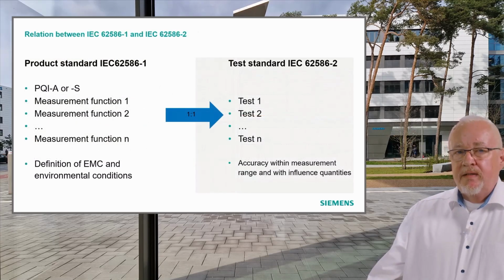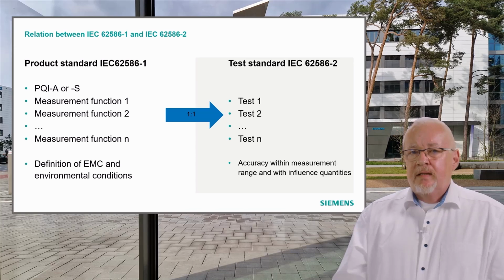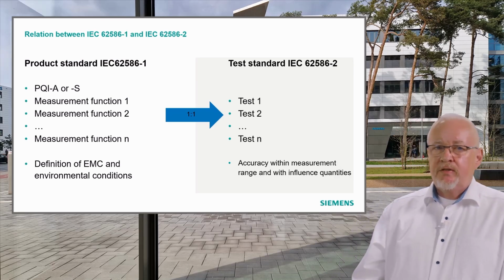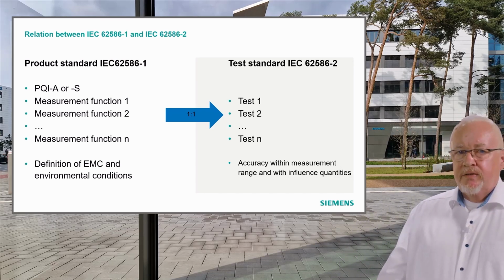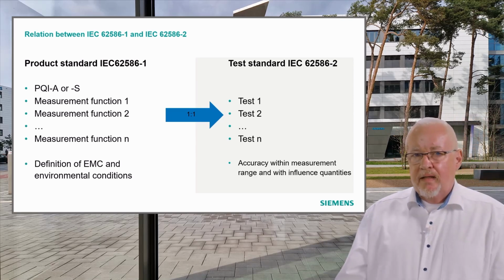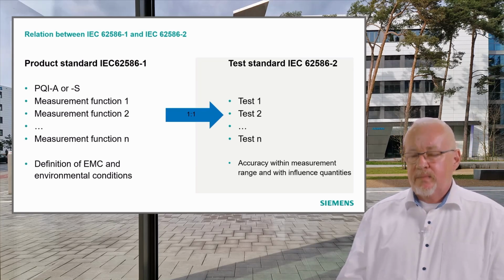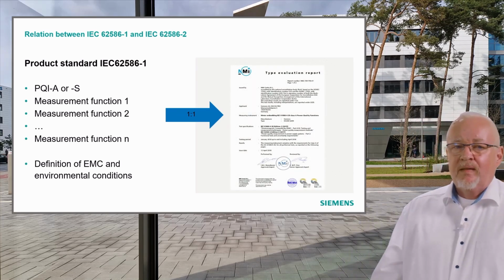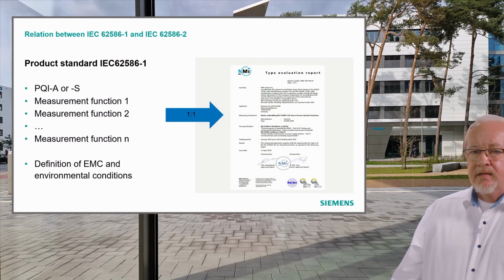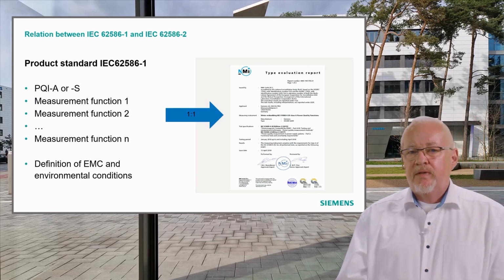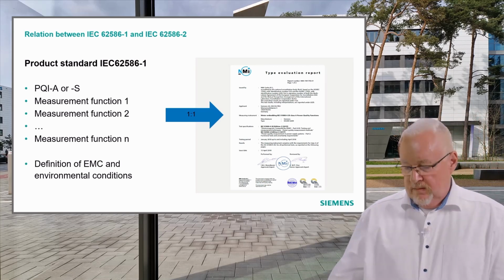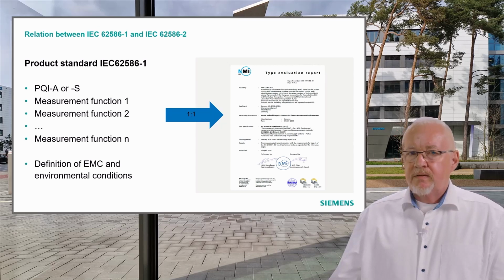There is a clear one-to-one relation between the product standard itself and the related testing standard, part 2. For each power quality measurement function, test procedures are defined. After manufacturer's internal function tests are passed, an external certification by a lab is usual and meanwhile required by customers. So we see here, if you pass all the tests, you can get a certificate from an external lab here from Netherlands, from NMI, and that's what the customer often likes to see meanwhile.